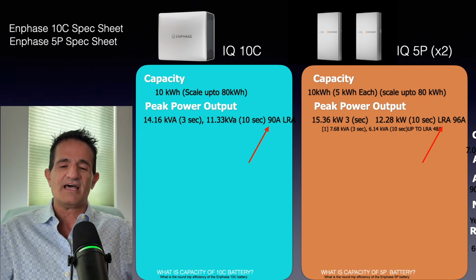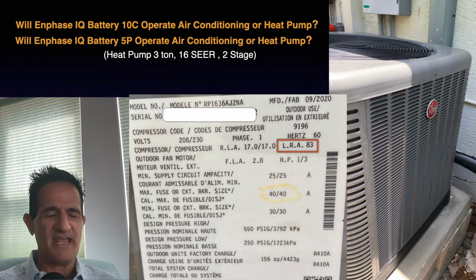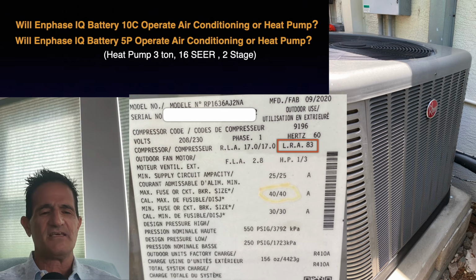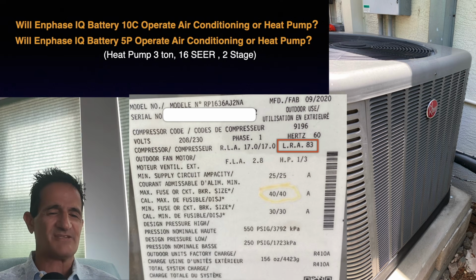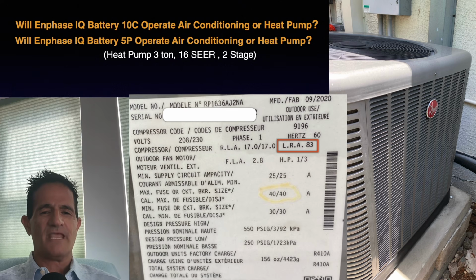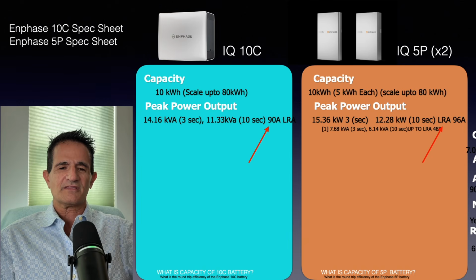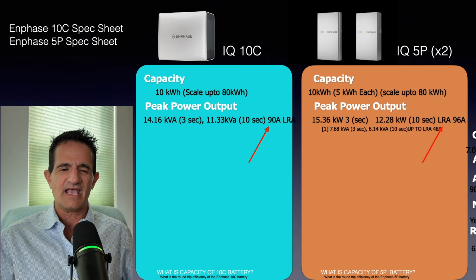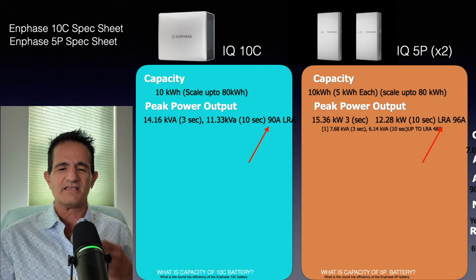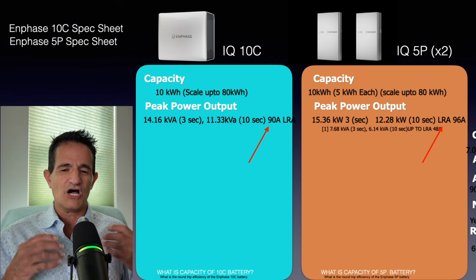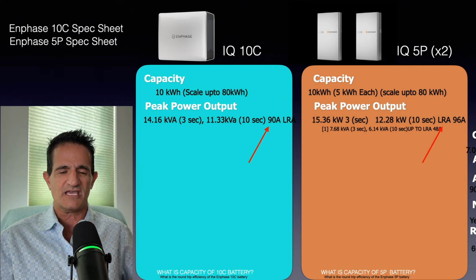And so let's review the LRA number. So people often ask, will the Enphase IQ Battery 10C operate an air conditioner or heat pump? And the same thing for a 5P. Now, in this example, it's a heat pump that's 3 ton, 16 SEER, 2-stage. Now, you have to check your own heat pump or air conditioner, and if you go to the back of the unit, you'll find a nameplate like this. On there, you'll see the LRA number. Now, I circled this one. It's 83 amps. So in this case, both the IQ 10C and the IQ 5P, if you get two IQ 5Ps, it'll power this heat pump. Now, if you have multiple air conditioners or heat pumps, then you may want to get more batteries, okay?